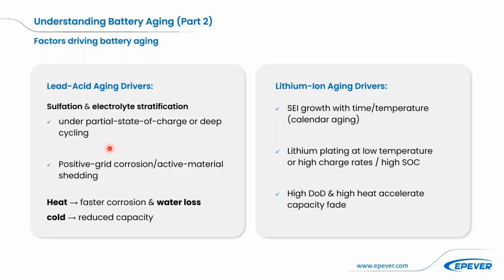So for lead acid, the biggest issue is sulfation and stratification when systems run at partial state of charge or are cycled too deeply. And if you add heat, you will speed up positive grid corrosion and water loss. In cold weather, you simply get less usable capacity, so you get faster wear.